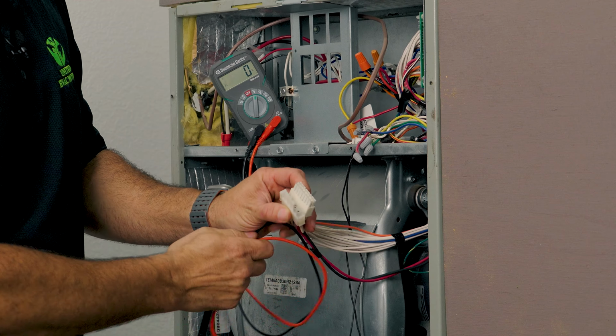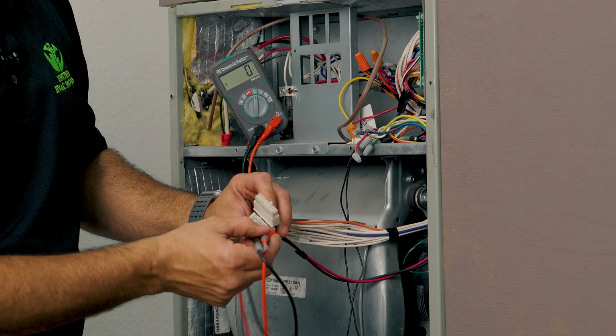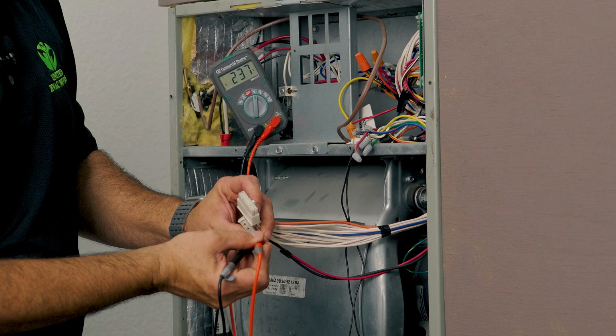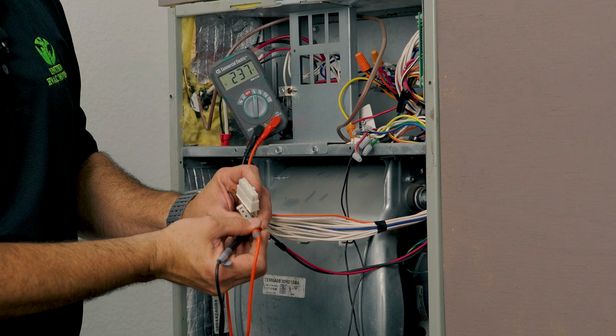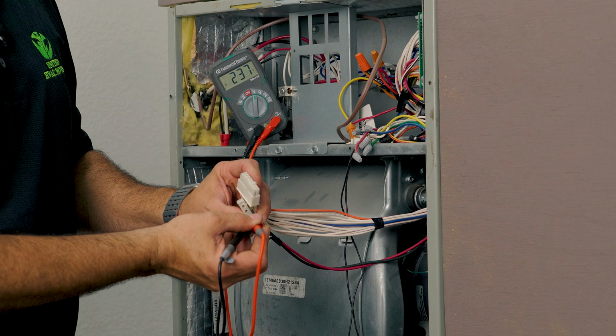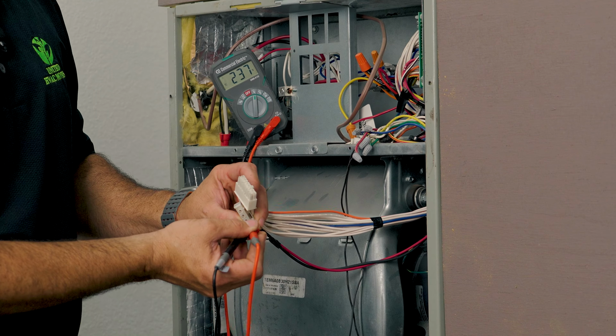You'll have your multimeter set to volts AC. The first thing you will do is test these last two right here for high voltage. In this case, we have 237 volts. This is a 220 system, so anything between 220 and 240 is okay.